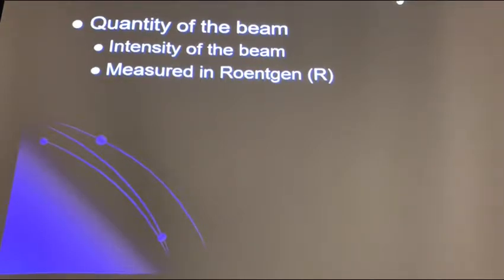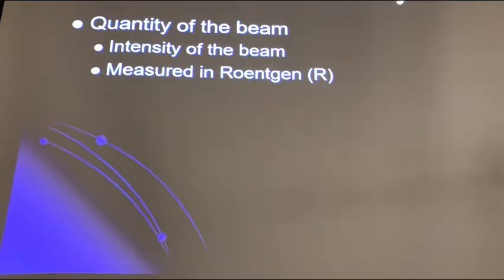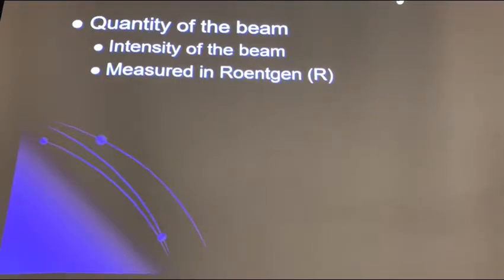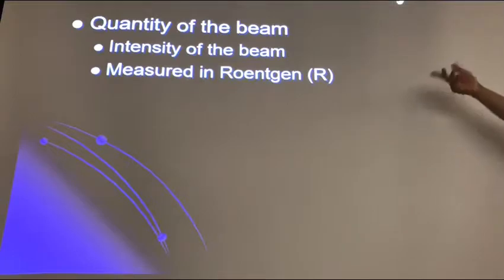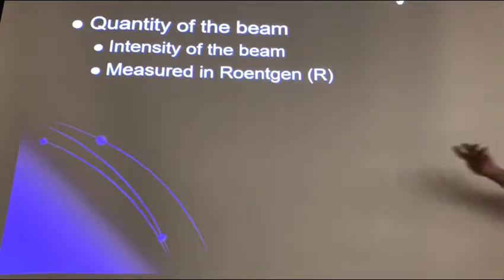Quantity and quality. By the way, about 70% of what we're going to cover in this section I've already talked about throughout the semester, so it shouldn't be too complicated. For example, quantity of the beam — we already talked about intensity of the beam. What controls that? MAS, KVP, and distance.